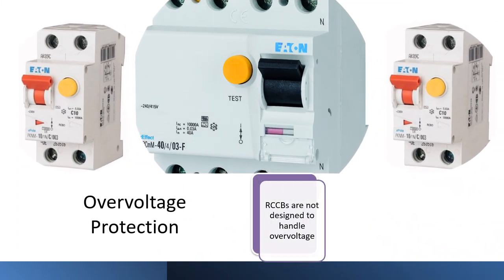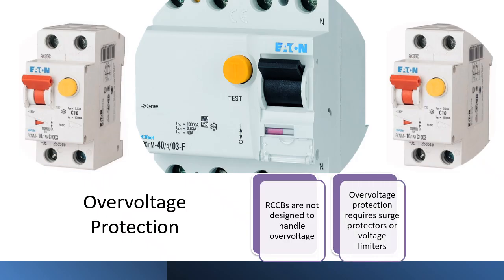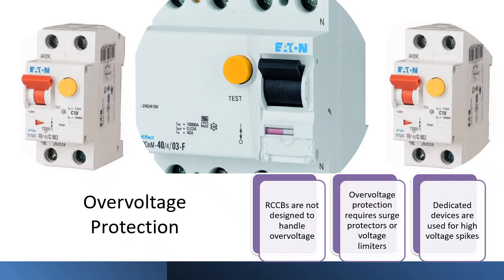Overvoltage protection. Now, overvoltage protection is a different matter. RCCBs are not designed to handle high voltage spikes. To safeguard against overvoltage, we need devices such as surge protectors or voltage limiters. These are built to absorb or block sudden voltage surges, which an RCCB alone cannot manage.